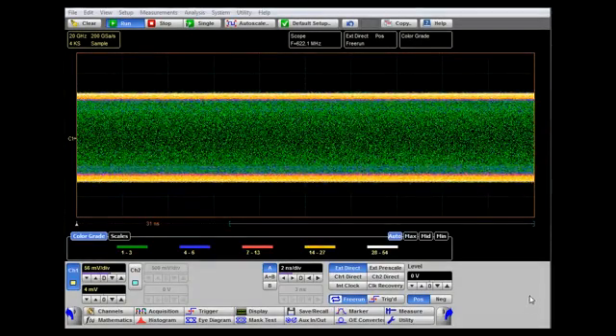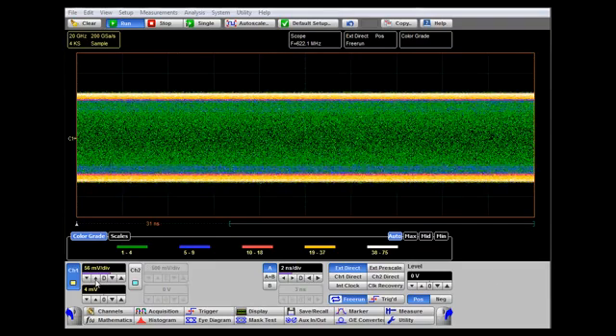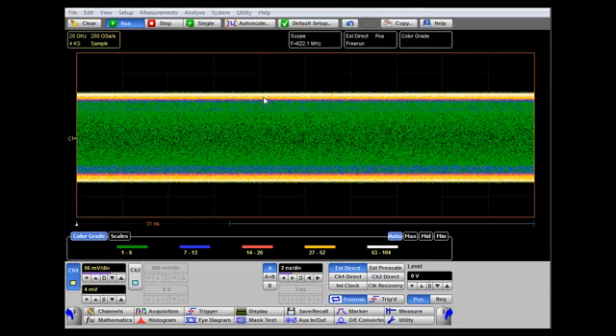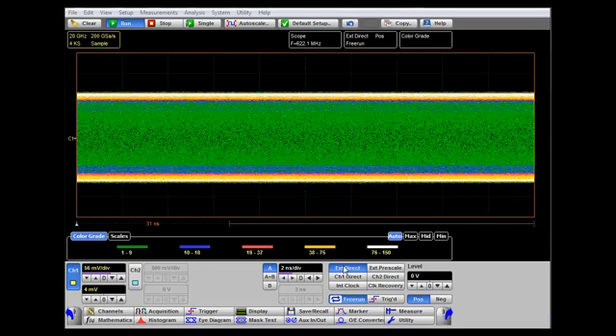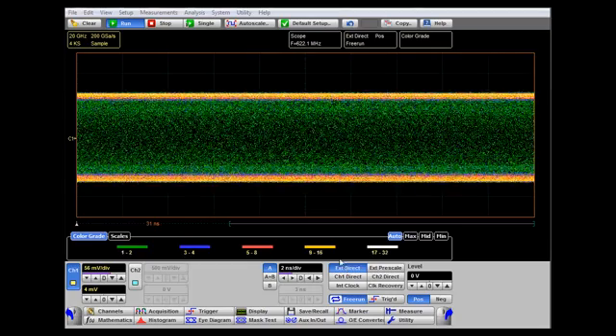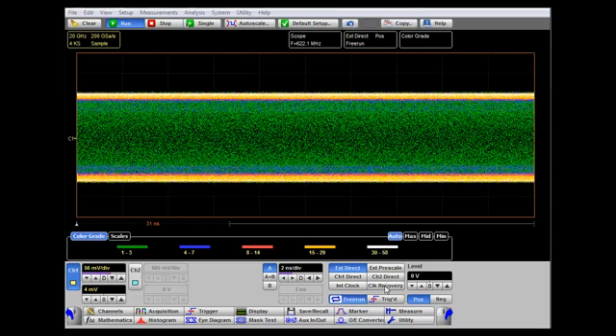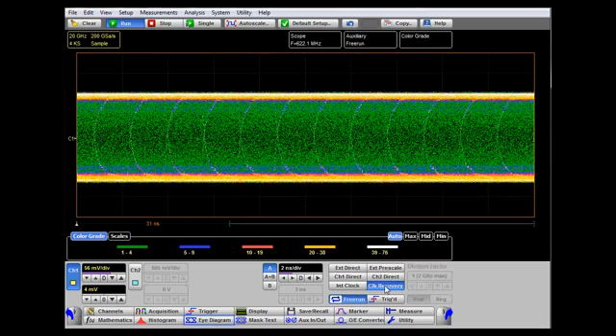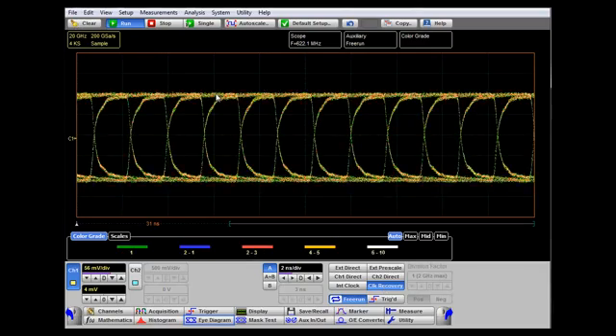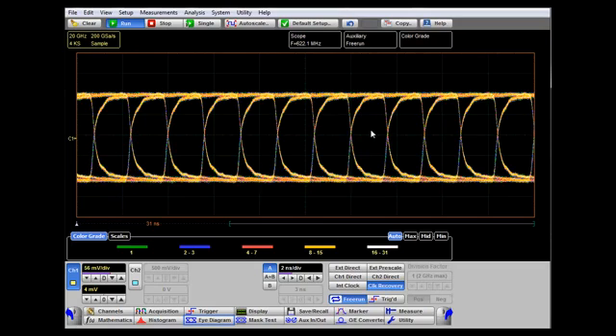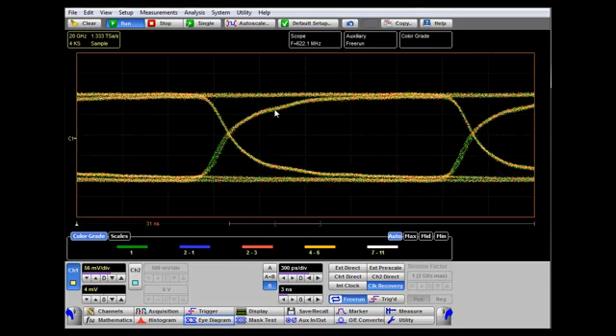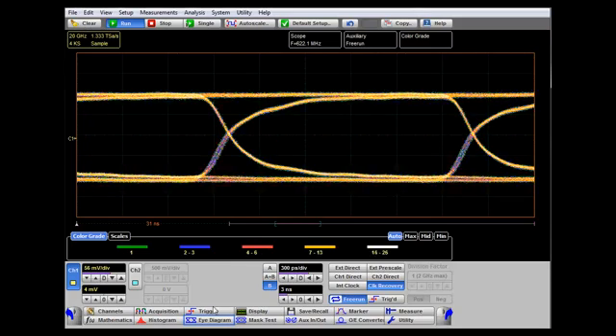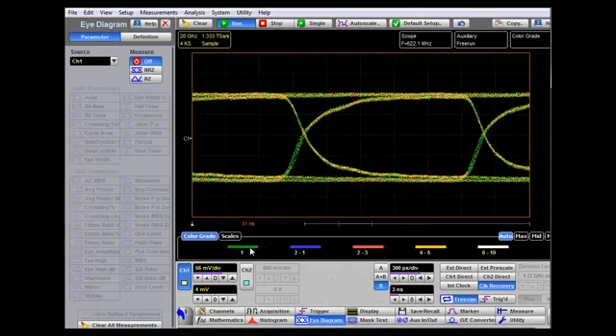In this third acquisition example, we have again connected the random data signal to the channel one input. The waveform is untriggered because there is no system clock available from the device under test. We send the random data signal via a divider to the clock recovery input, then select the clock recovery trigger input. Clearing the display, we can see a triggered display with several eyes available. Switching to the B delay time base and clearing again shows a single eye.